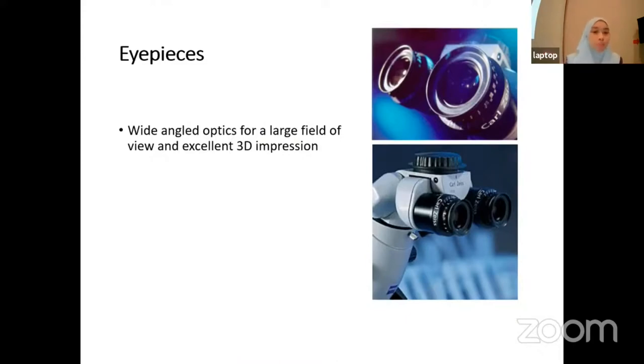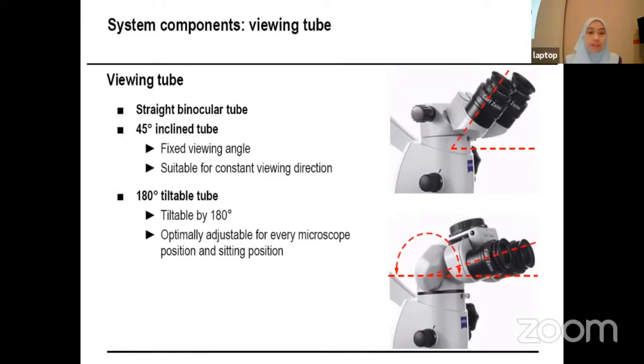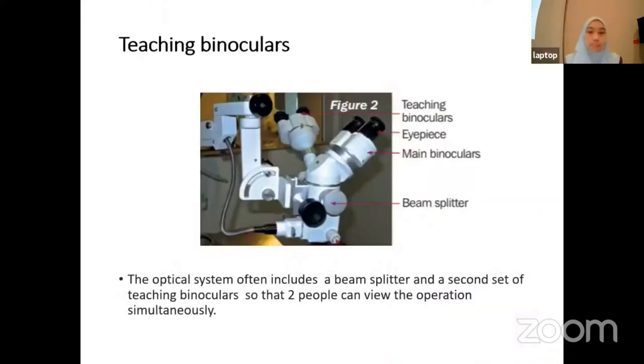The eyepiece provides wide-angle optics for a large field of view and excellent 3D impression. For the viewing tube, we have a straight binocular tube or 45-degree inclined tube with a fixed viewing angle, suitable for a constant viewing direction. We also have a 180-degree tiltable tube, which can be adjusted to get the optimal position. Most microscopes currently also have teaching binoculars, which include a beam splitter and a second set of binoculars so that two people can view the operation simultaneously — very useful for the assistant or a supervising teacher.